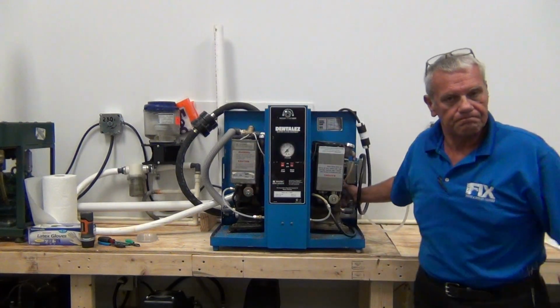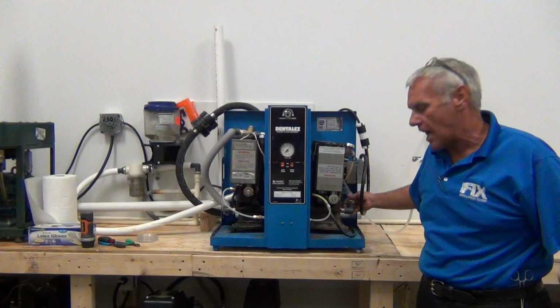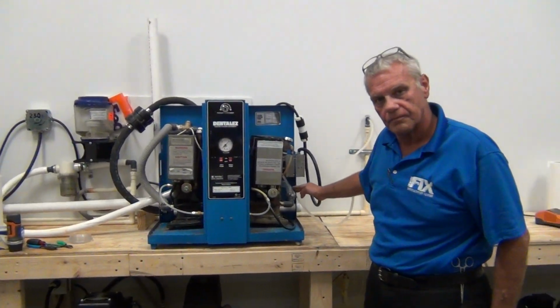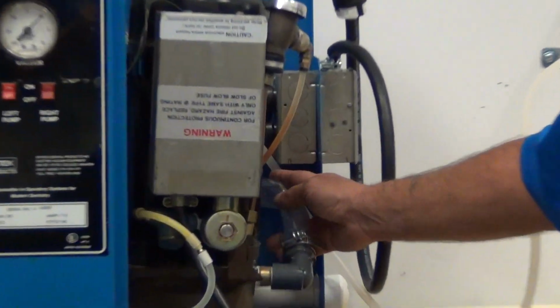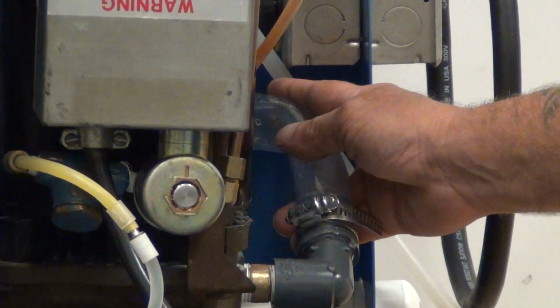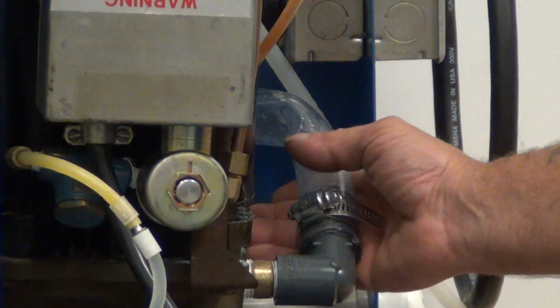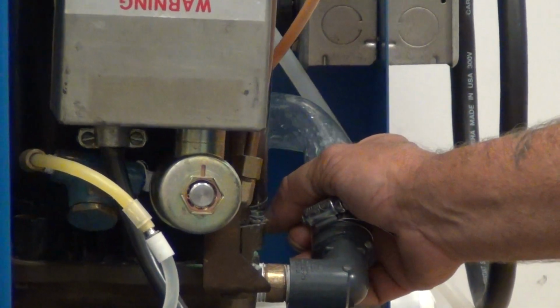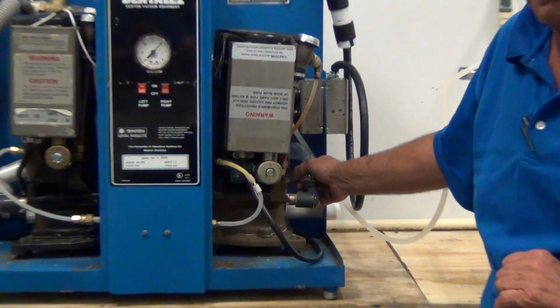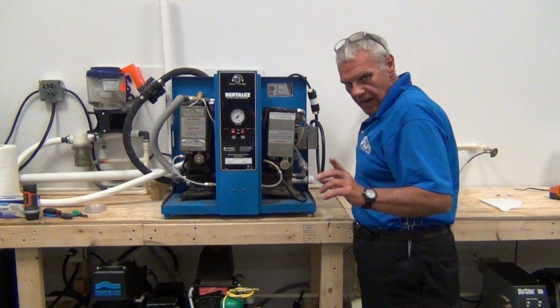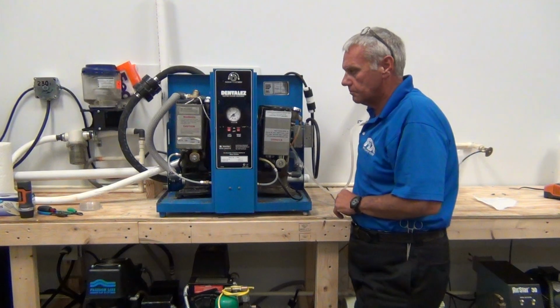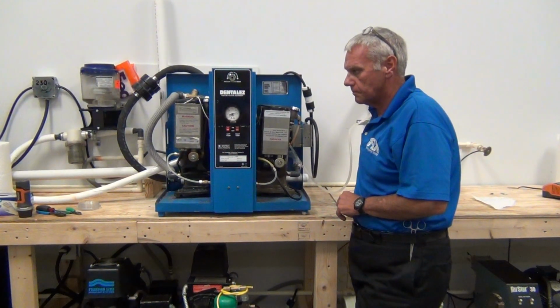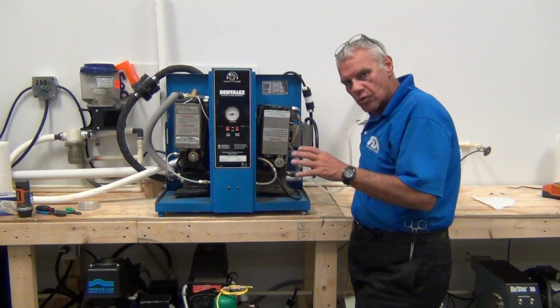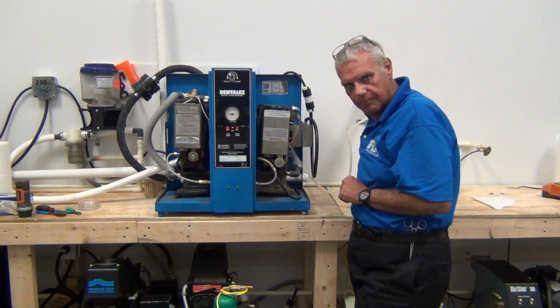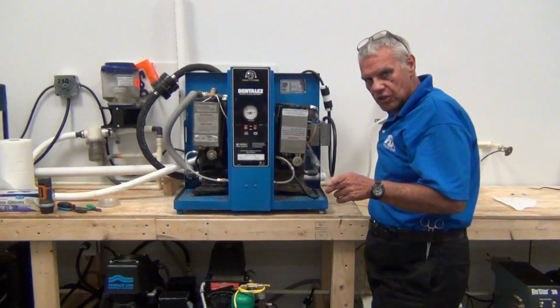To do this quickly, we've installed clear tubings on the exhaust side of the pump. We can actually see the water exhausted through the clear tubing. You can see the water going up through the tubing. The pump will have a high-pitched whine and will run very hot without water. I'm going to illustrate the sound difference to you. Hear the difference in the sound as well as a noticeable drop in your inches of mercury. I'm going to restore the water back. You can actually hear the difference in the pump.